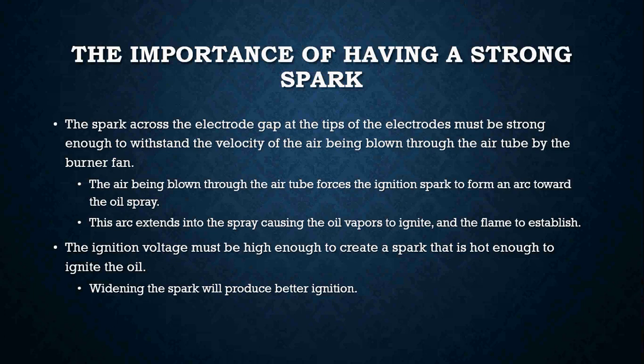So it's really important to make sure that we have a spark that is strong enough so that we can actually ignite the oil. Because remember, the spark across the electrode gap at the tip of the electrode must be strong enough to withstand the velocity of the air being blown through the air tube by the burner fan.